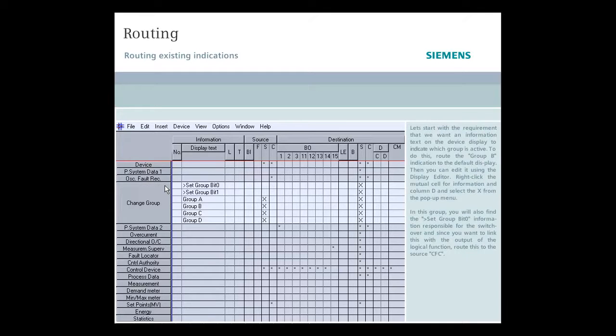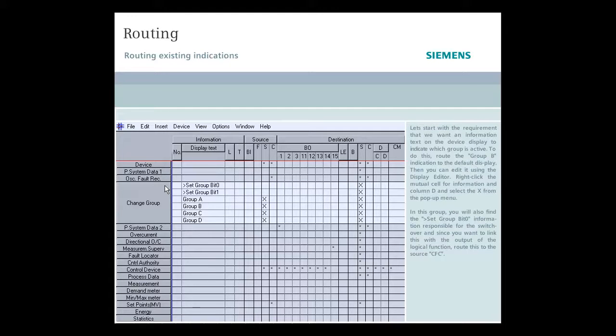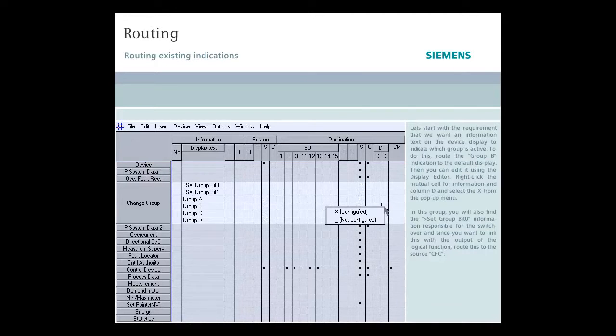Let's start with the requirement that we want an information text on the device display to indicate which group is active. To do this, route the Group B indication to the default display. Then you can edit it using the display editor. Right-click the mutual cell for information and column D, and select the X from the pop-up menu.